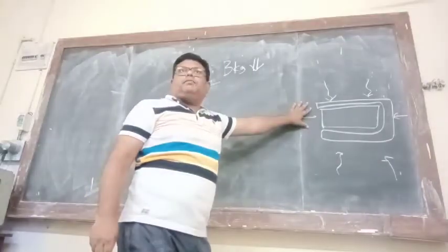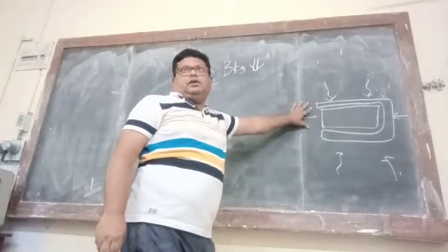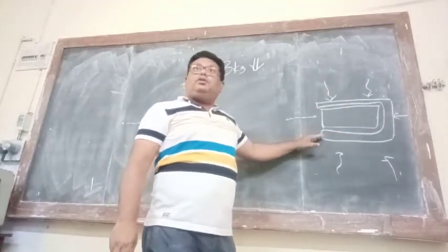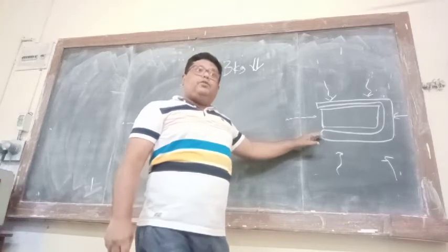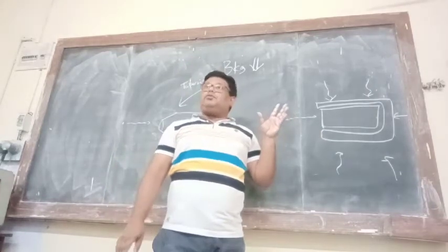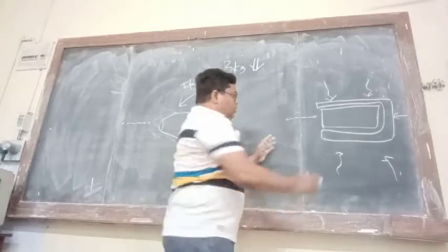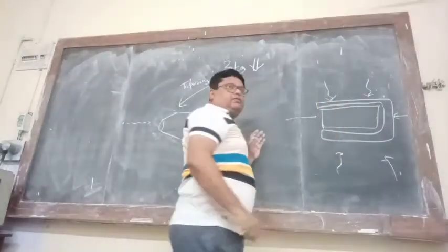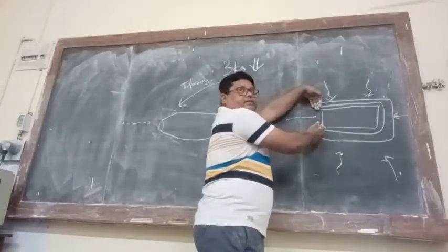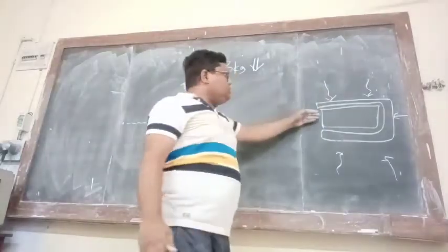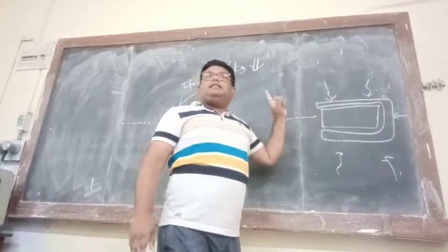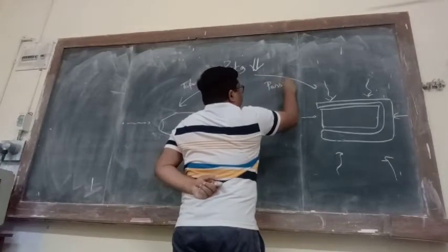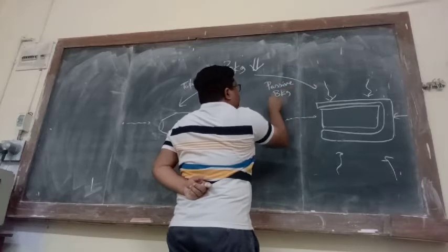I will put a protective material outside the detector which will protect it from the radiation. So what I am going to do is choose a material which has a very high photoelectric effect cross section, so that whatever comes gets absorbed over here, and as a result it will not be able to interact with this, but this side will be kept open so that the source related gamma rays enter this. This is called the technique of passive background suppression.